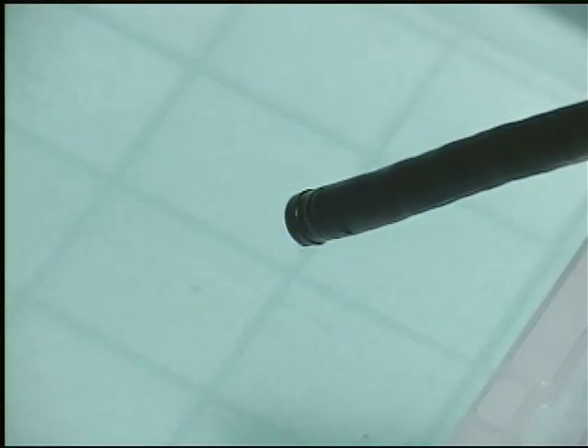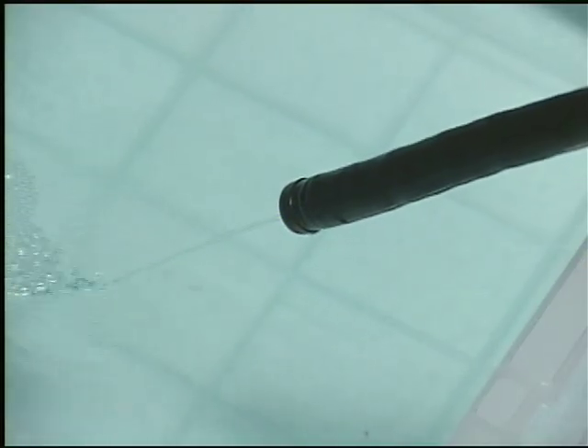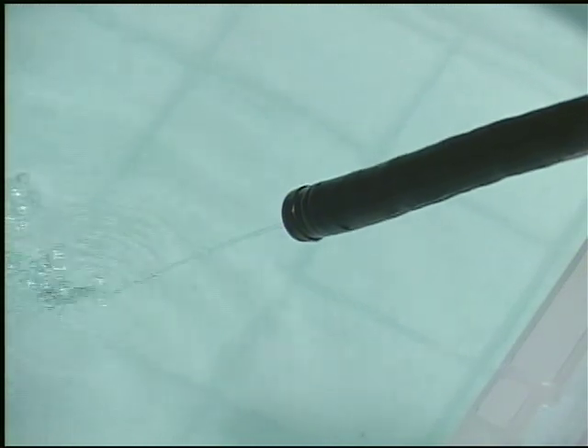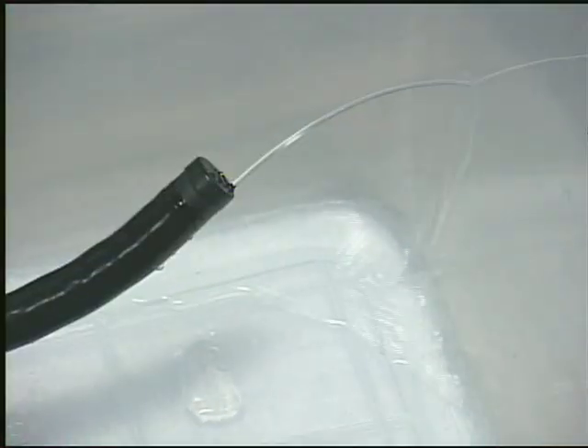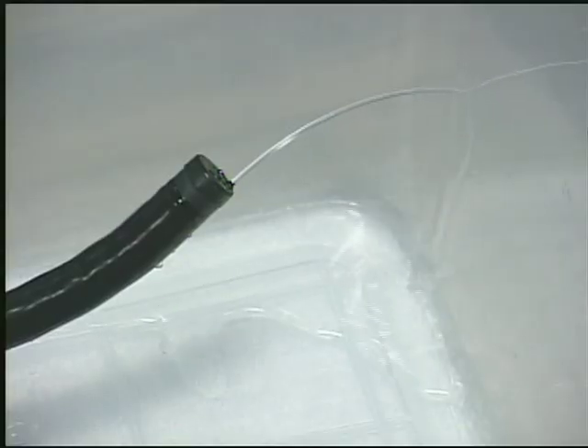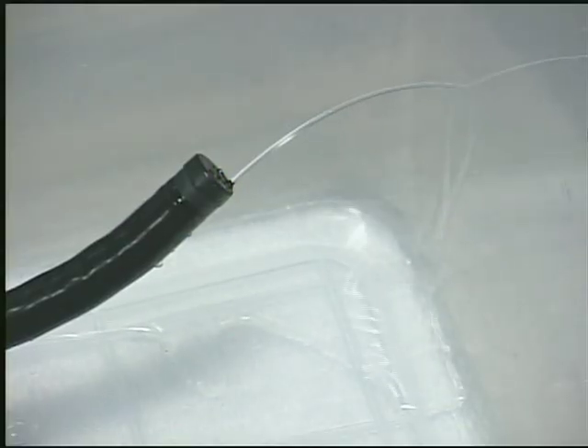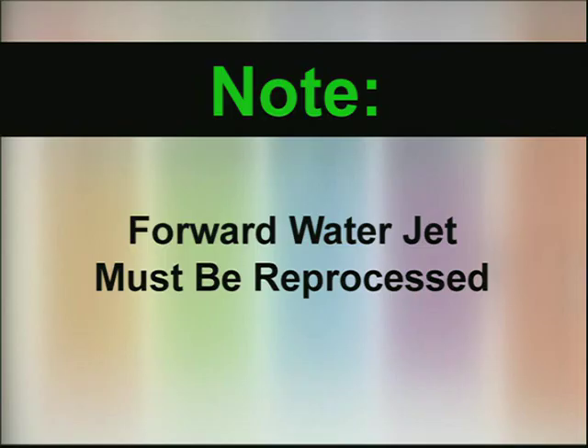The Pentax water jet feature allows physicians the ability to shoot a forceful stream of water at a target site via a manually operated syringe or a foot-controlled irrigator pump. It should be noted that regardless of whether the water jet system was used during a procedure, it must still be reprocessed before every patient use.